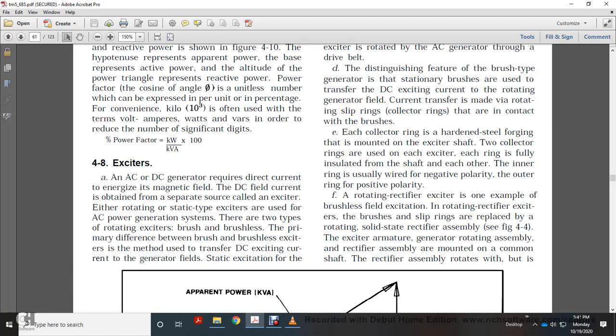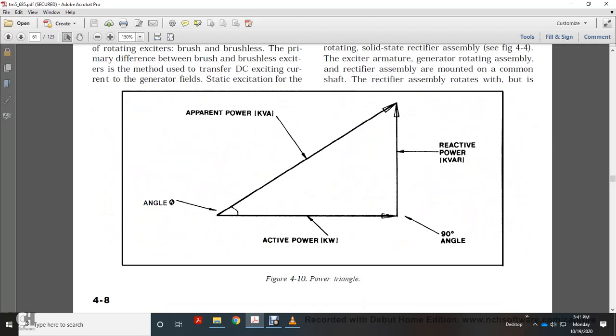Rotating rectifier exciter: one example of brush field excitation with the rotating rectifier. Excitation brush with slip rings is replaced by a solid state rectifier assembly. The exciter armature with the generator rotating assembly is mounted on a common shaft, and the rectifier assembly rotates with it. Shown is the power triangle, with the angle zero, the apparent kilovolt amp, the kilowatt at 90 degrees, and the reactive kilovolt amp.